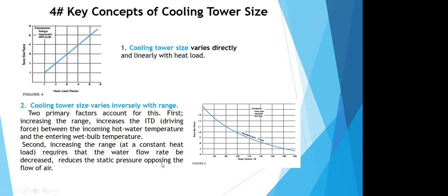If you see in this graph over here, if I have a unit tower size for a unit heat load, if I double the heat load at the same approach, we double the size of the tower. So this is pretty straightforward, and I think most of us know about this. The second key point about the cooling tower size is that it varies inversely with the range at a constant heat load and a constant approach.